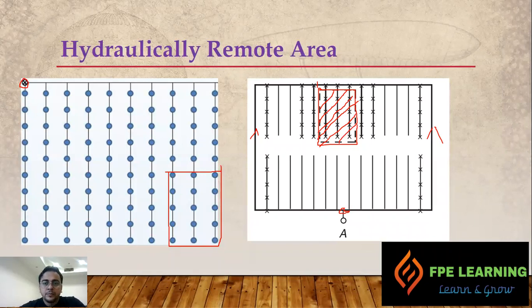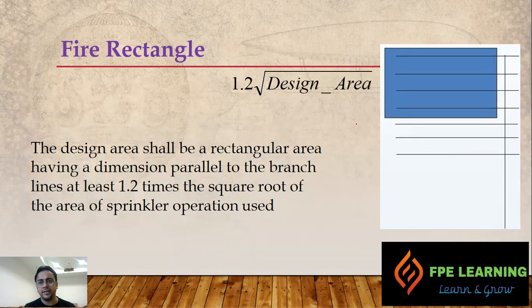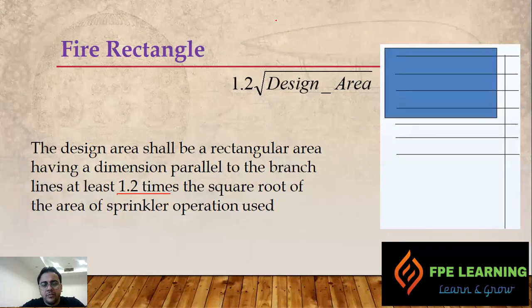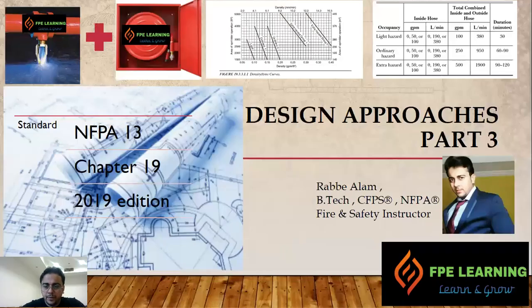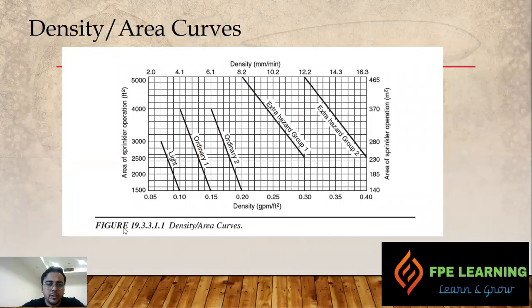Next we have the design areas, the fire rectangle. The design area shall be rectangular having a dimension parallel to the branch line at least 1.2 times the square root of the area of sprinkler operation. Let's say if your project is for OH-1, going to the graph.